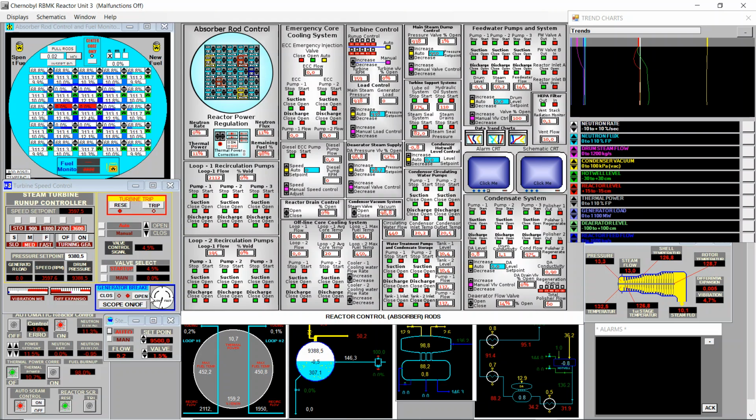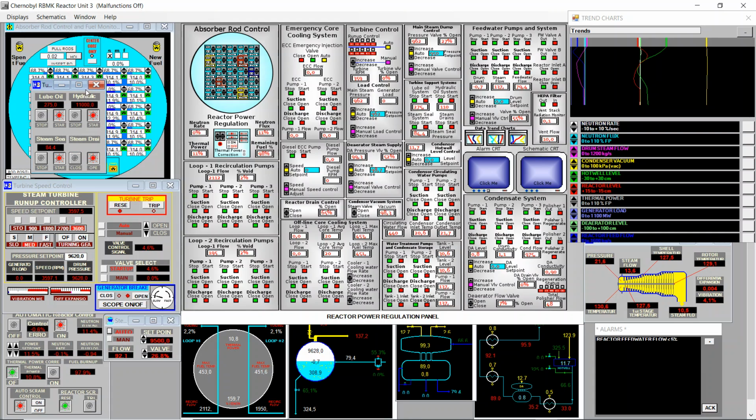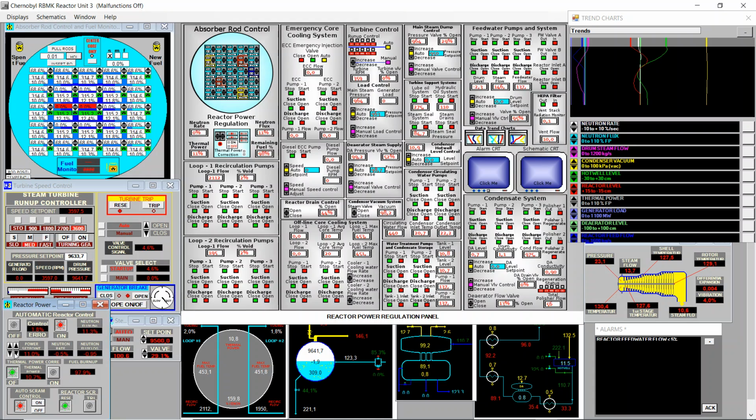I'm afraid to close the brake here because I think I will have a turbine trip if I don't succeed to close it at the top dead center. Why does the speed keep at exactly 3597? That's quite strange. All these settings are fine. I will decrease back the power set point to 10.